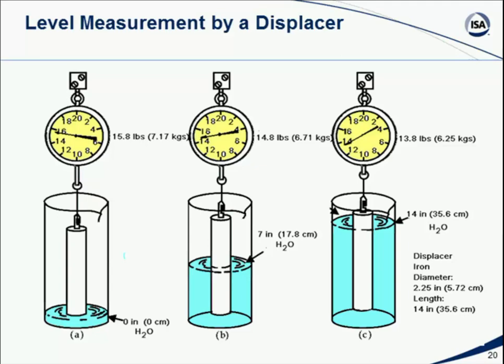And in the final diagram, the displacer now is, shall we say, fully submerged, or at least submerged to the maximum level of liquid that we're going to allow in the tank. So the water level is now up to 14 inches in the tank, and the displacer's hanging weight is now down to 13.8 pounds. So what have we seen here?